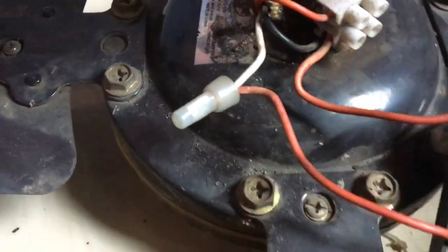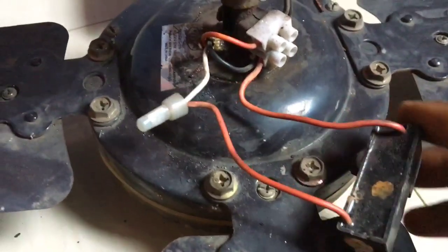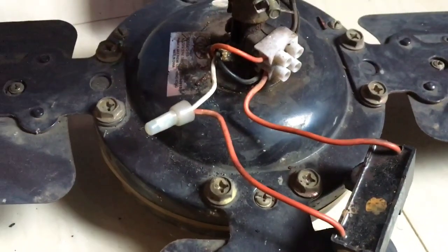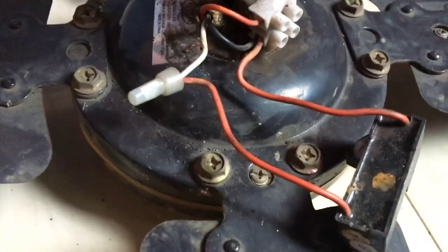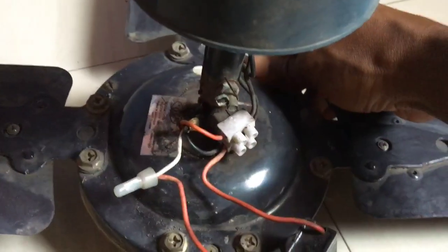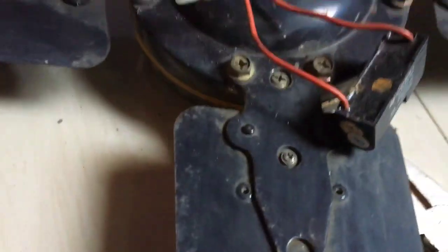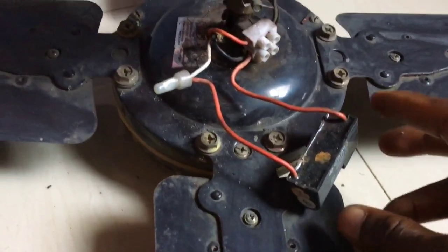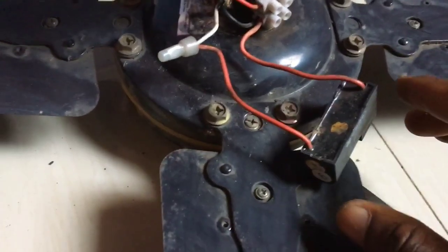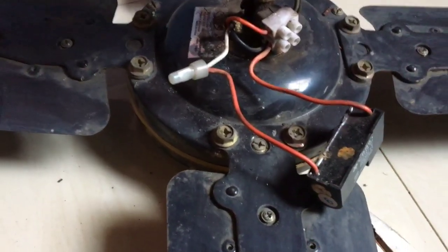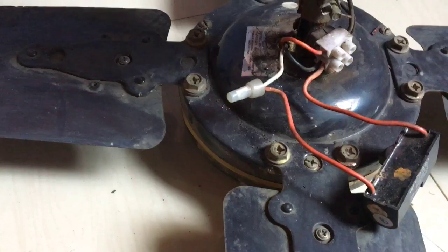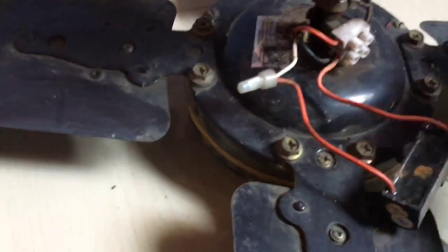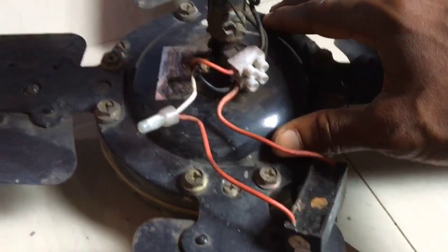Then the next thing to suspect is your capacitor. And most of the time, if your capacitor is bad, you'll be hearing a hum sound and the temperature of this coil will become very high. You'll be hearing a hum sound and the temperature will be high, or the fan will be spinning slowly. So these are the signs that your capacitor is bad. But if you're not hearing any sound at all, the temperature is not high, or it's just hot and is not spinning, you start to suspect a bad or a faulty coil.